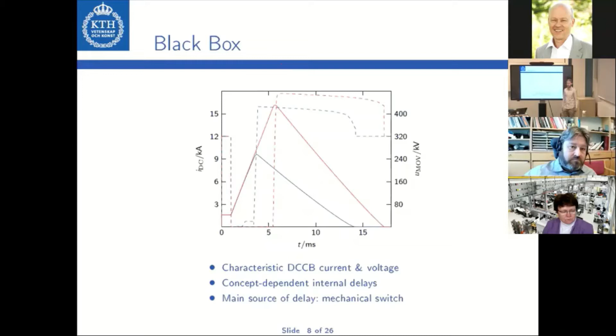The main source of delay of a DC circuit breaker is the mechanical switch. Every practically relevant DC circuit breaker uses a mechanical switch in the main path to guarantee low losses. However, mechanical switches open much slower than it is, for instance, possible to switch a semiconductor, and hence it is not possible to avoid such delays.